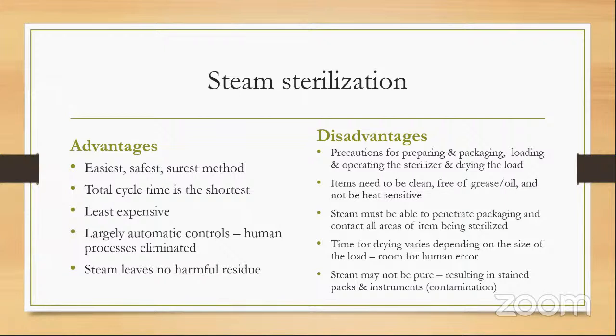One big disadvantage is that the steam may not be pure. And if the steam is not pure, then the whole load would be not just stained, but contaminated. And usually there is no way to know this unless the specific quality assurance runs are being done routinely. But sometimes you won't know until you see a package comes out and it is stained. Then that should raise a red flag about the quality of the process.